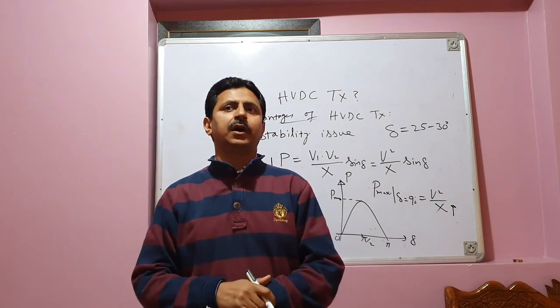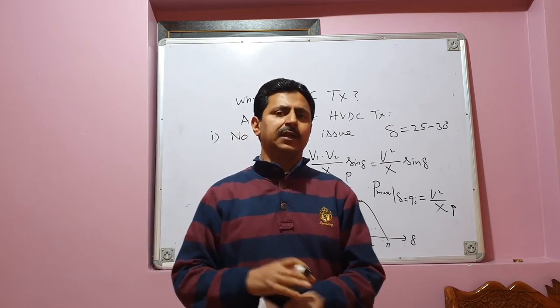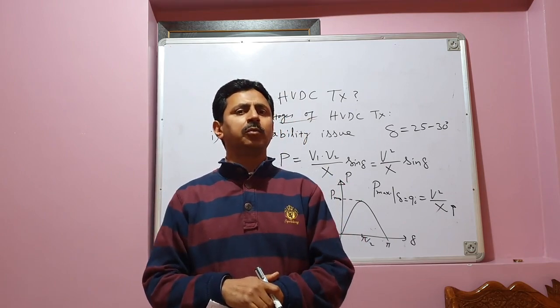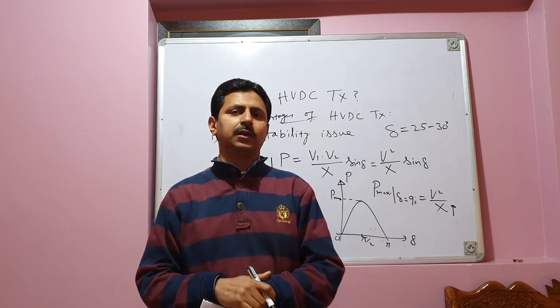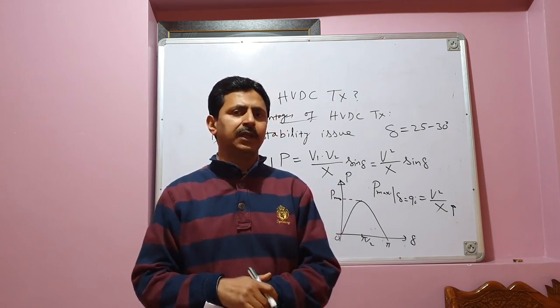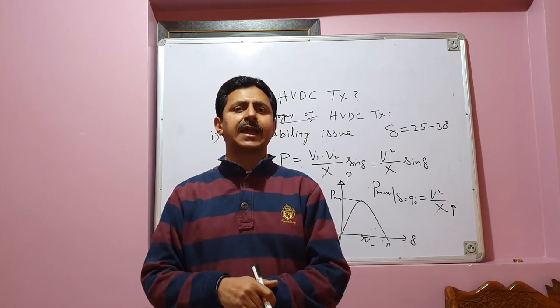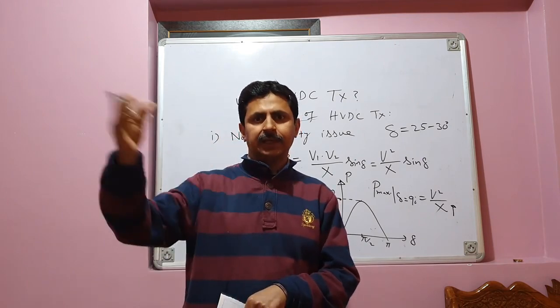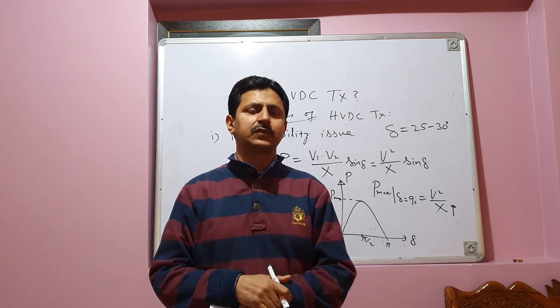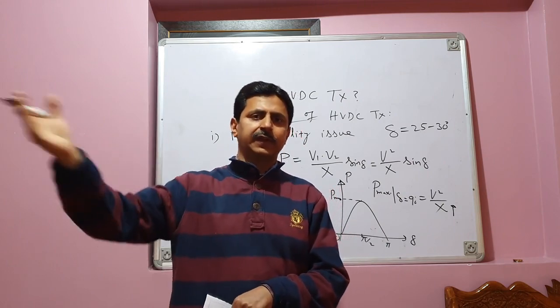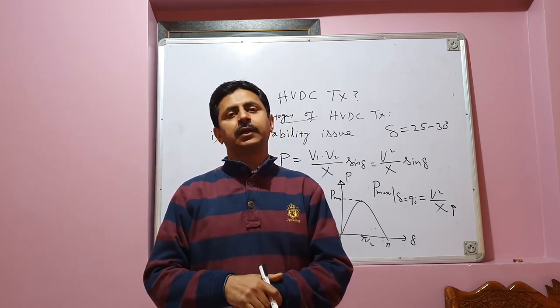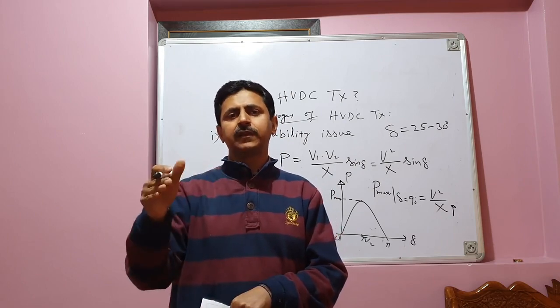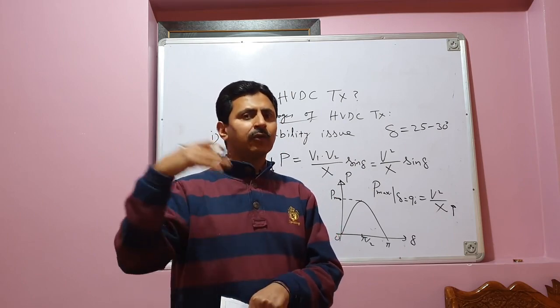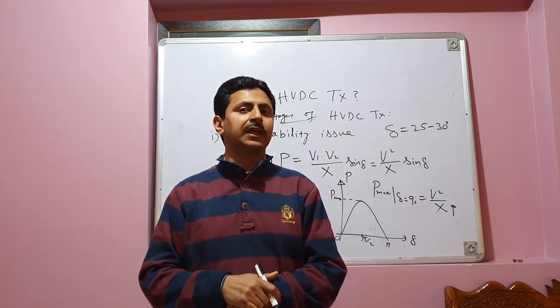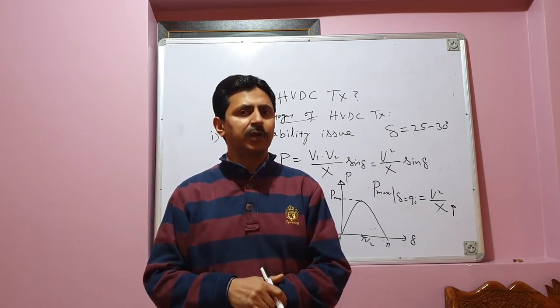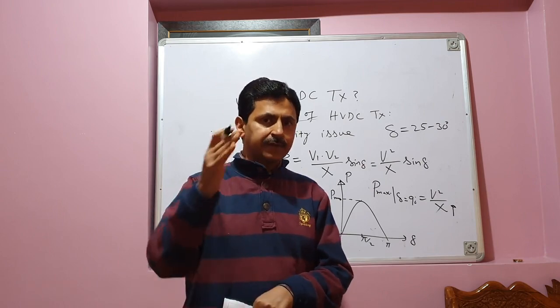That means, for example, in the first case, let us suppose that we have a 500 kilometer long transmission line and we are transmitting 100 megawatts of power, and the reactance of the line is X1. Now, if we extend the length of the line from 500 kilometers to say 800 kilometers, we add 300 kilometers more, the reactance will increase. It will increase from X1 to X2. Therefore, the line will not have the capability of transmitting such a large power. So, as X increases, P decreases.